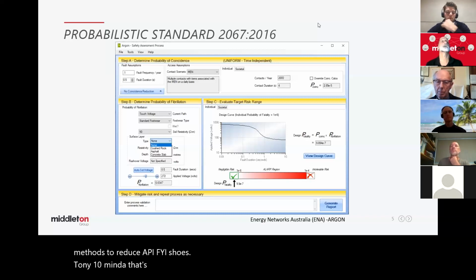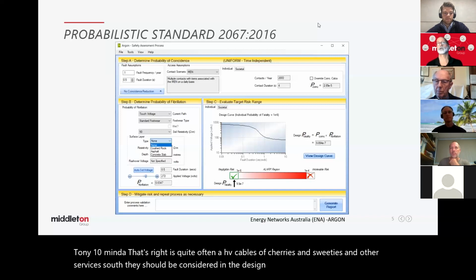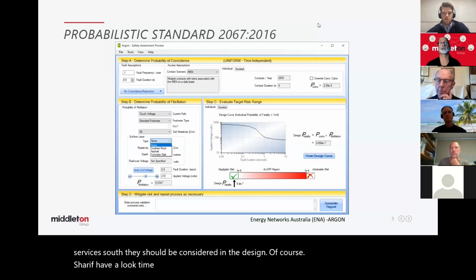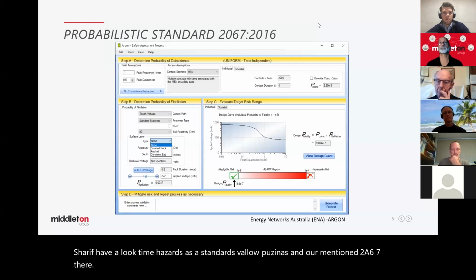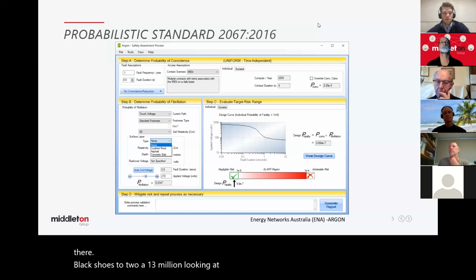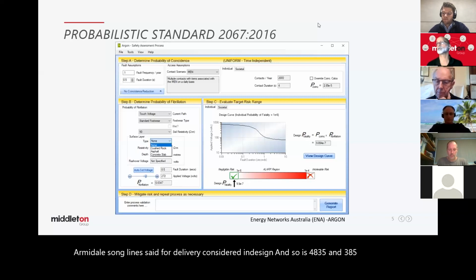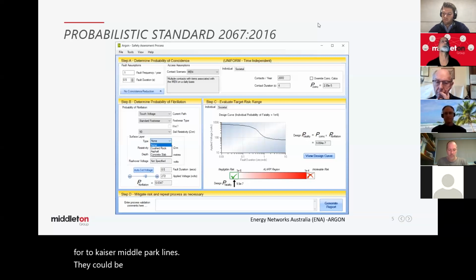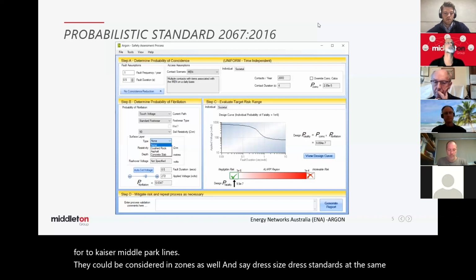Well, that's right. Yeah, there's quite often the HV cables will share easements with other services. So they should be considered in the design, of course. So if you have a look at other standards, designers, I know I've mentioned 2067 there. We don't just use the 2067 when you're looking at third-party appurtenances, gas pipelines, CP points, air valves on lines, etc. They've all got to be considered in your design. There's 4835 and 3853 standards for telcos and for metal pipelines. They've got to be considered in designs as well. So yeah, address those standards at the same time in your design. I hope that answers the question, or is it a deeper question?